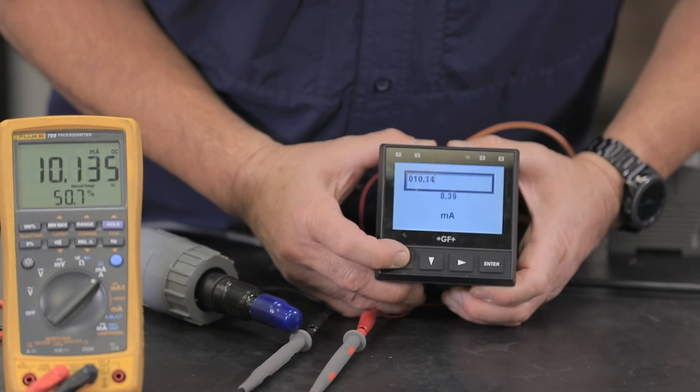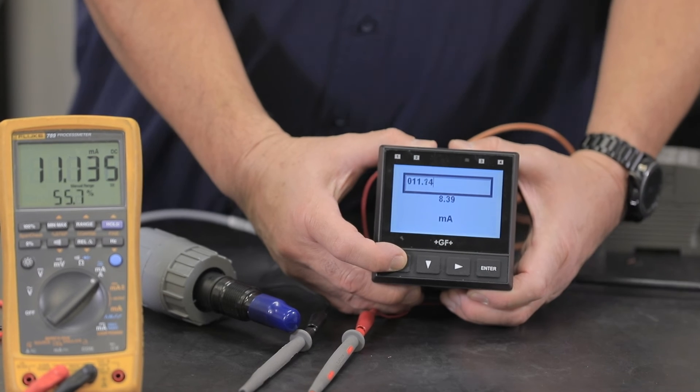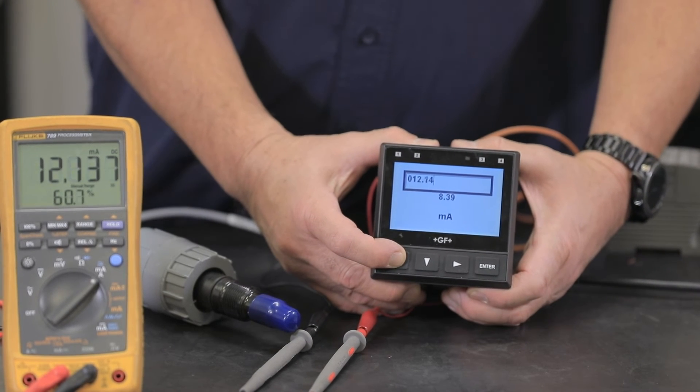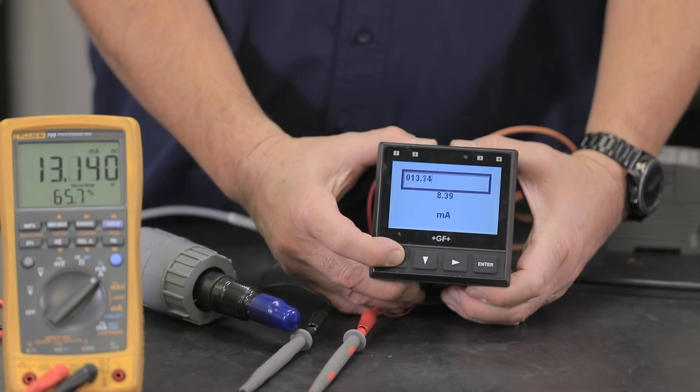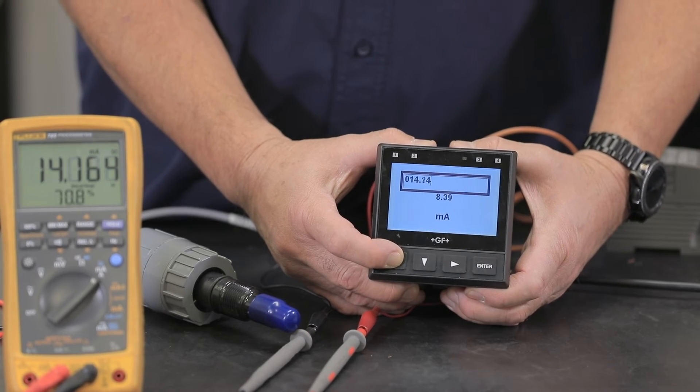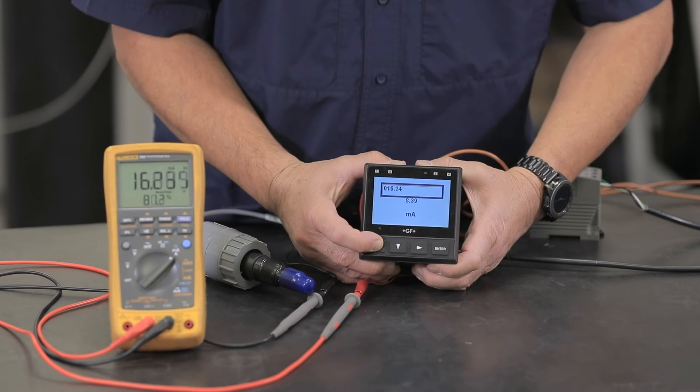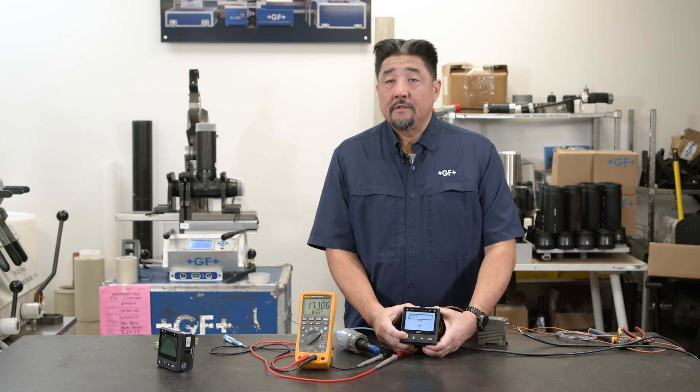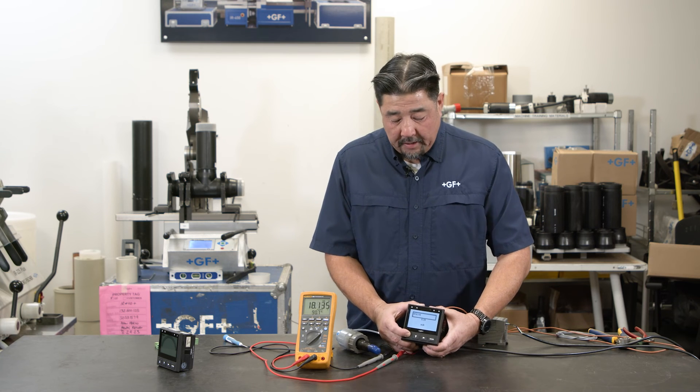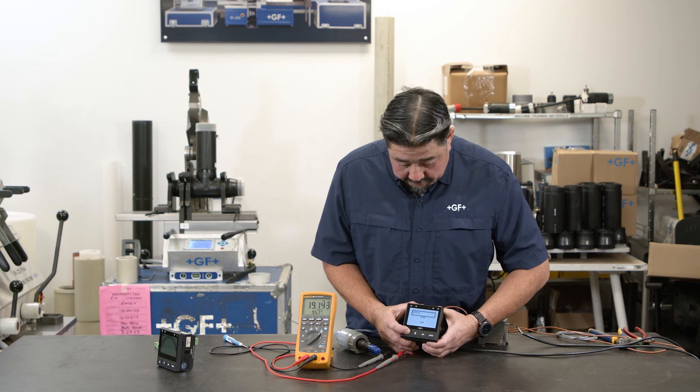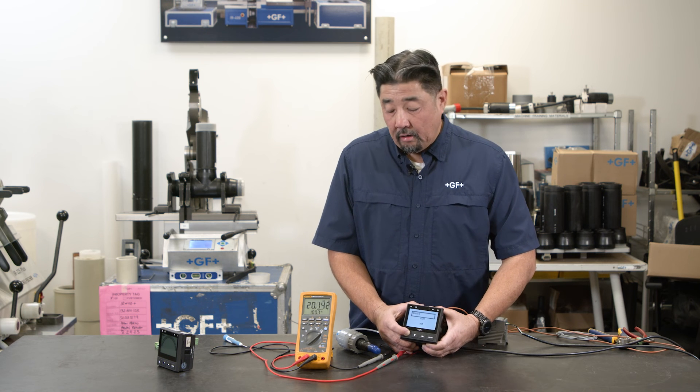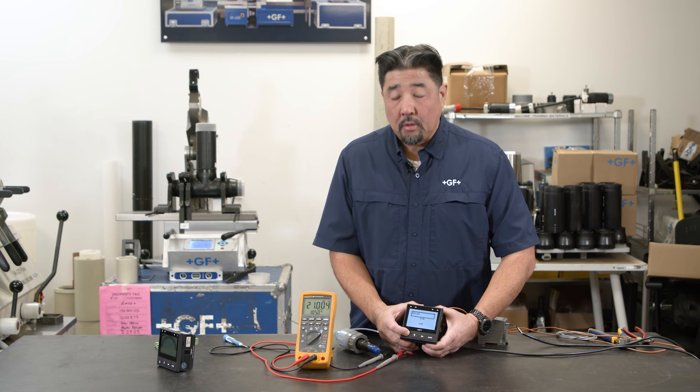And here as a signal generator I can manually set the 4 to 20 output. So if we're working with a 4 to 20 milliamp device and we don't know what the scaling is, we can manually ramp this up to 20 milliamps to see what our PLC or our HMI is displaying for 20 milliamps. It'll allow us to scale our 9900 or 9950 accordingly.